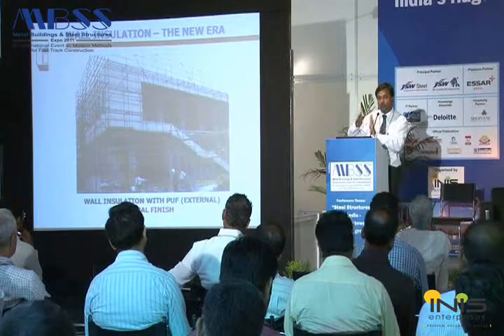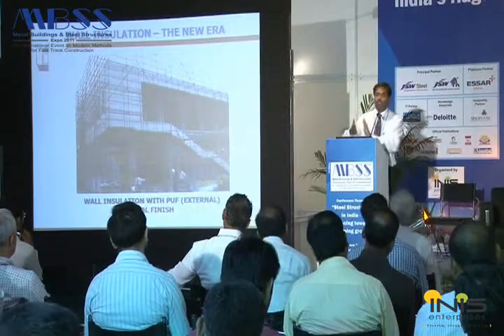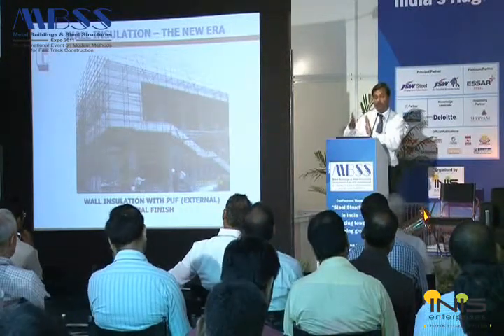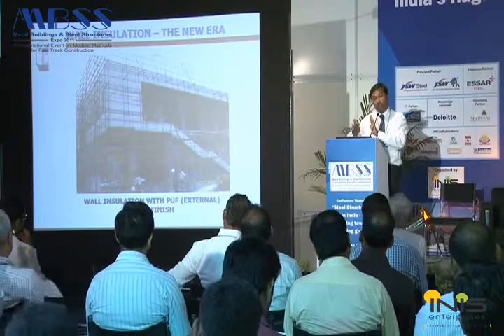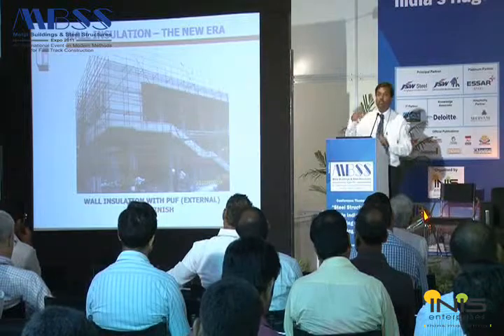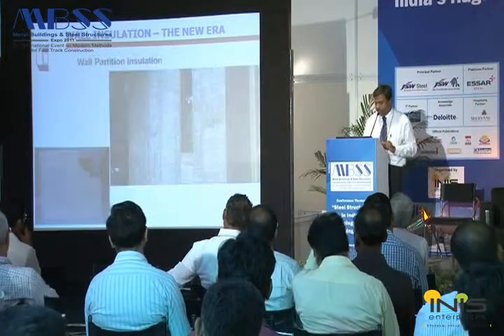That is the reason why polystyrene foams are not much successful in India as compared to polyurethane. Because polystyrene foams have a temperature rating of around 65 degrees centigrade or maximum 70, whereas urethane foams can go up to 110 degrees centigrade.